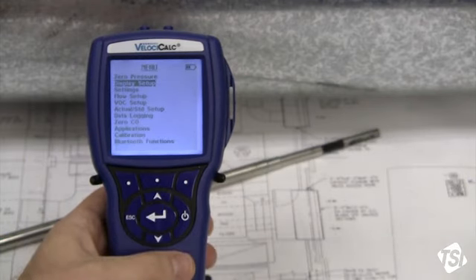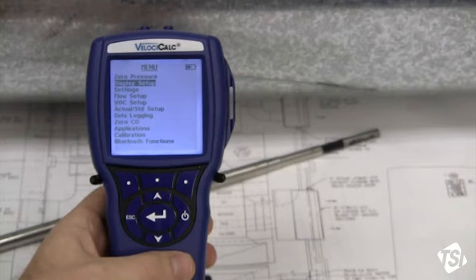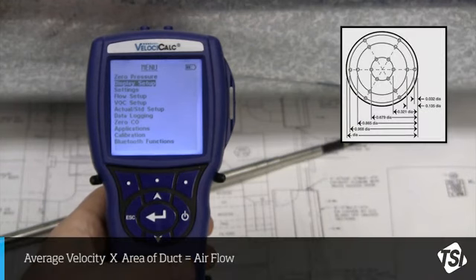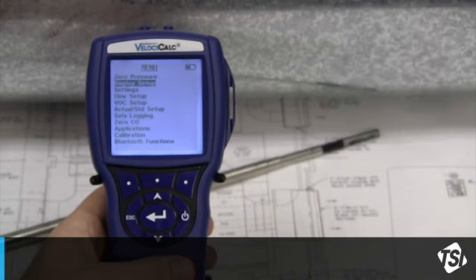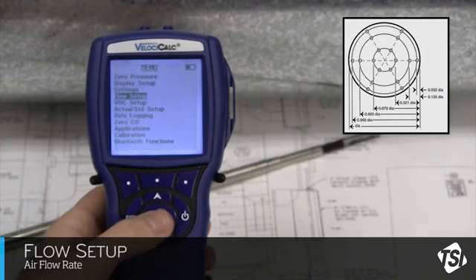Now we need to set the correct dimensions for my duct into the Velocicalc. Remember, airflow is calculated by multiplying velocity and the square footage of the area being measured. While back in the main menu, arrow down to Flow Setup. Press the Enter button.